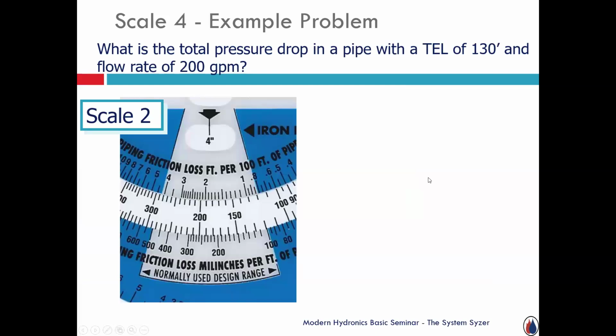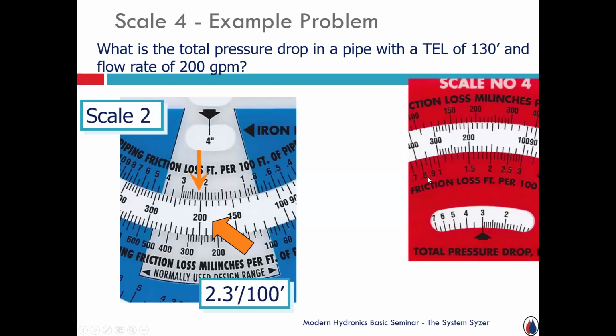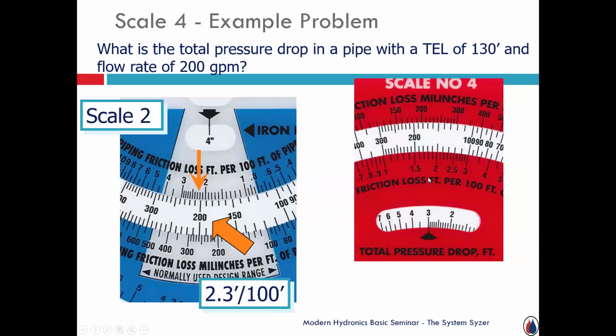Same thing that holds true on that scale 2. We're saying, hey, what's the TEL for 130 feet with a flow rate of 200 gallons a minute? What size pipe? 4-inch. Okay. 200 GPM is about 2.2, 2.3 feet per 100. 2.3, we'll call it. Now I flip it over, go to scale 4 and say, hey, what's my total? TEL is 130. So I'm just going to find 130 in the scale here, 100, 110, 120, 130. Opposite, about 2.3, read straight down. It's just a calculator. And it's saying it'd be 3 feet of pressure drop.